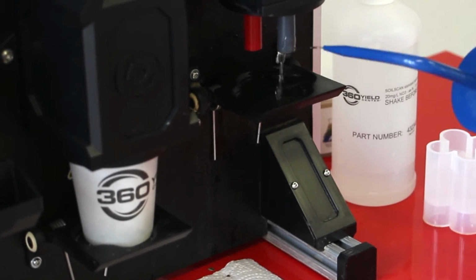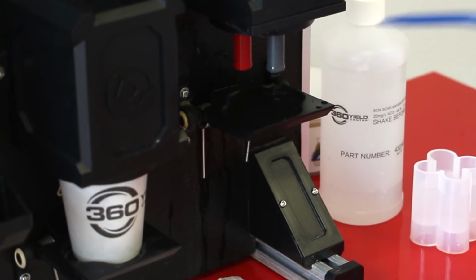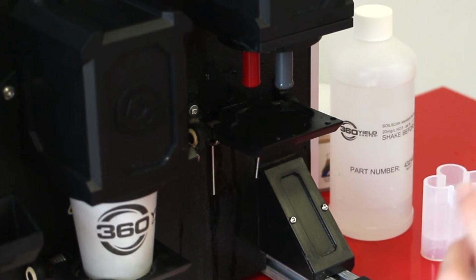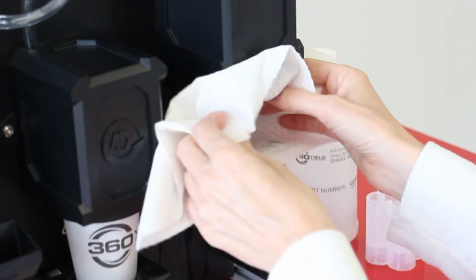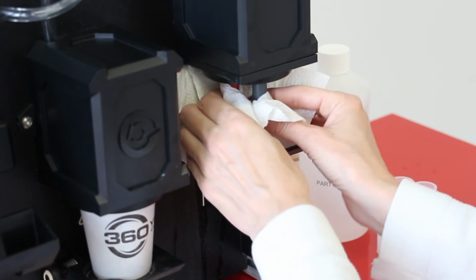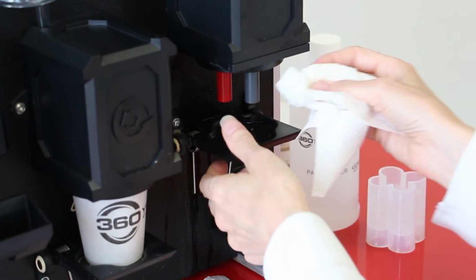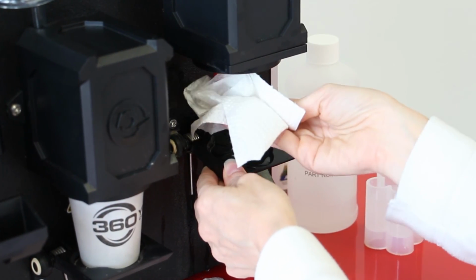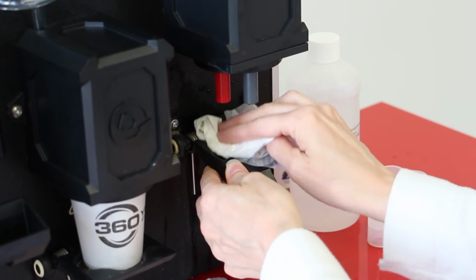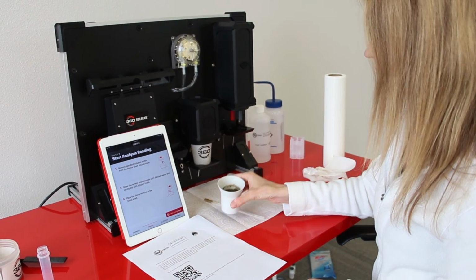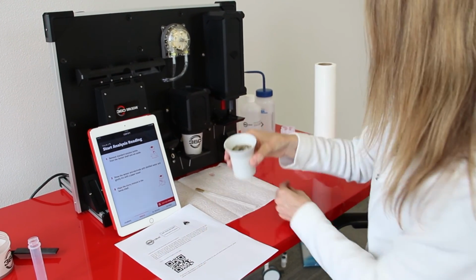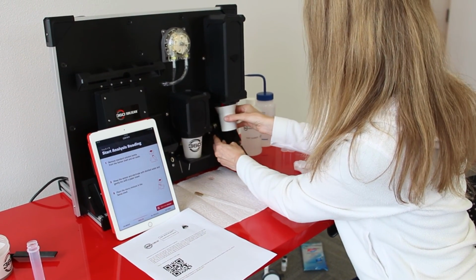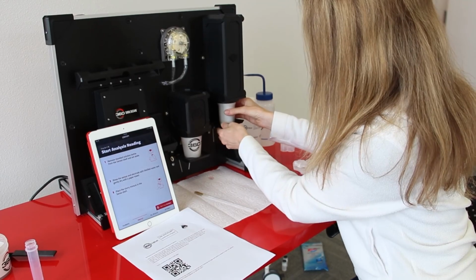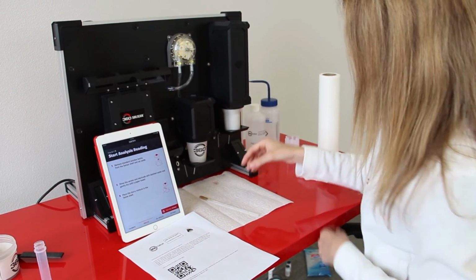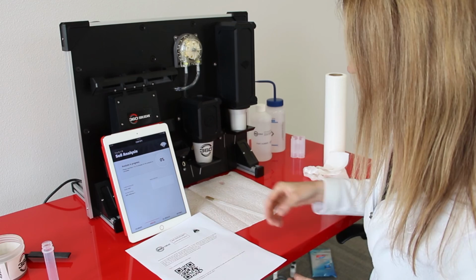Just give it a pretty generous squirt on both of that electrode and the nitrate sensor, and take a paper towel and you can just wipe the sides down, and then remember to pat the bottom of your sensors. We don't want to wipe the bottom of the sensors because there is a protective cover on the bottom of that too, so we don't want to damage the sensor that way. The next step you do is you take your slurry mixture and you place it on the sensor shelf so that the sensor and the reference electrode are soaking in it. And then you hit next step, analyze.